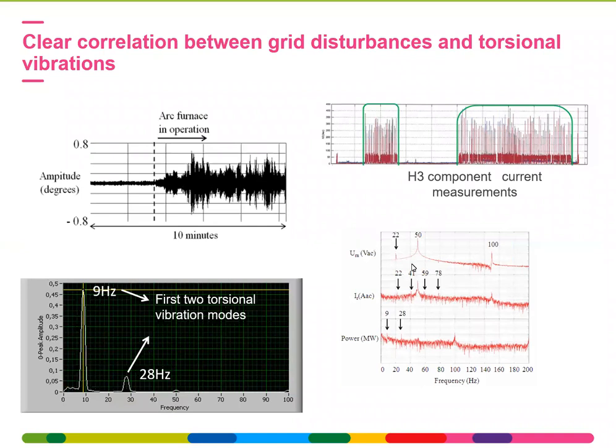From the electrical measurements, you can clearly see that there's a coupling between the mechanical and the electrical part. The fact that there's disturbance on the grid is shown in the H3 component of the current. The fact that the torsional natural frequencies are coupled with the grid is shown by the measurements, because the complement of the frequencies in torsion are shown in the voltage and current measurements. So the 28 hertz is shown at 22 hertz, for instance, and the 9 hertz is shown at 41 hertz. This is a typical example where you see the coupling between the grid, the electrical arc furnace, and the power plant.